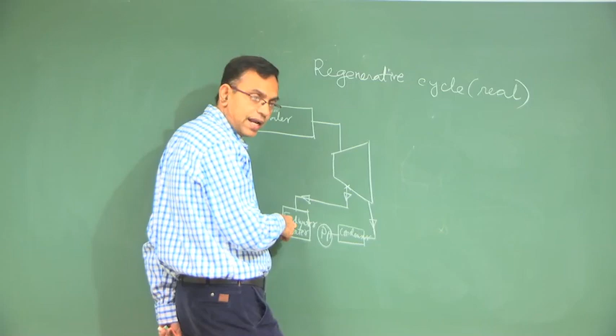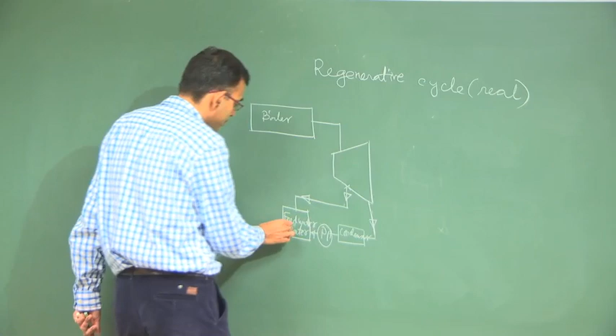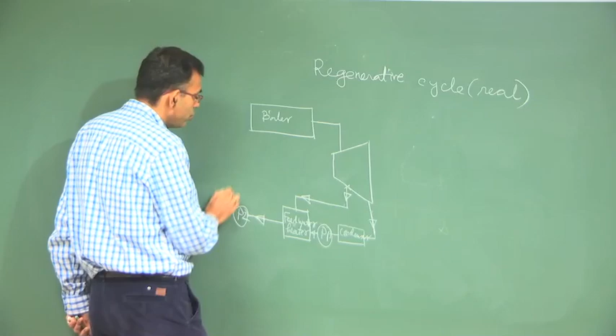But the remaining steam expands, it goes through a condenser, and then the condensate is pumped by pump number 1 to this intermediate pressure, because the fluids which mix in the feed water heater directly should be brought to the same pressure. So, this is already at a higher pressure than this. So, this pump elevates the pressure of the condensate to the pressure at which the steam is extracted. So, this fluid, which is relatively cold now, mixes with this hot fluid and it becomes hotter, and then it is pumped by another pump to the boiler pressure.